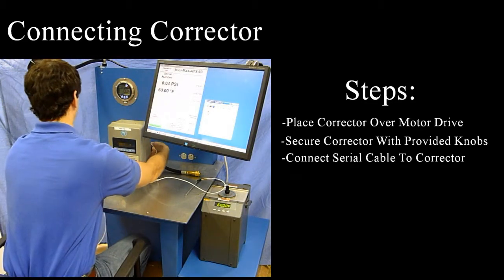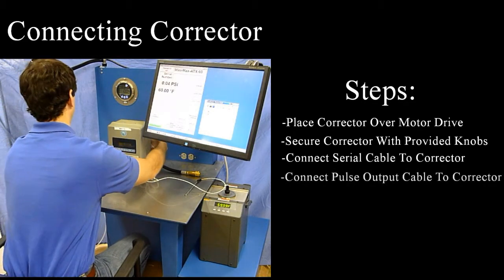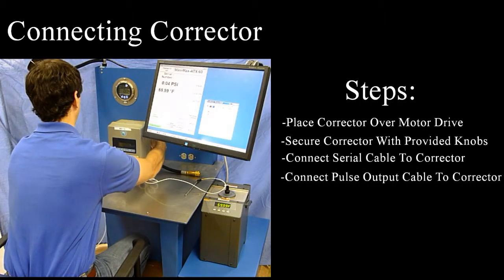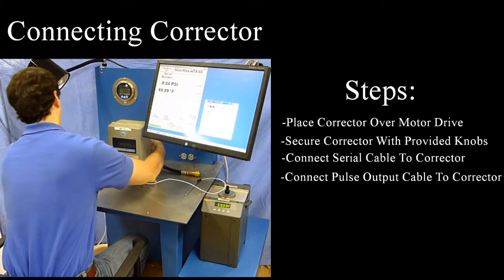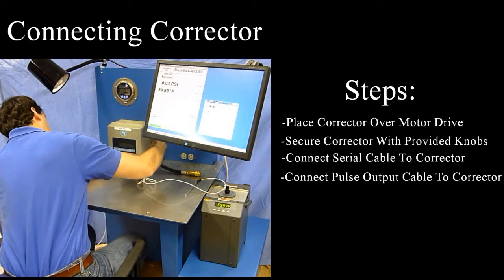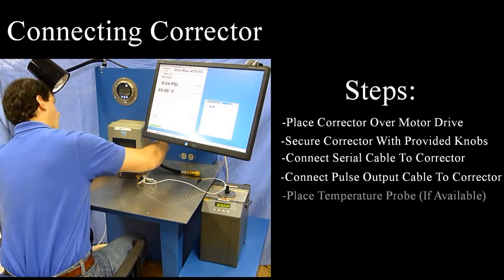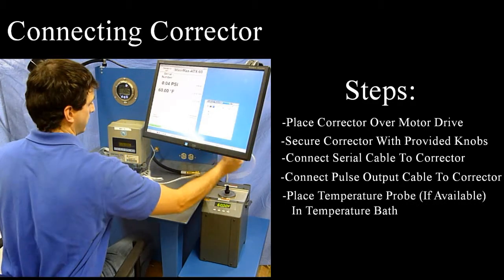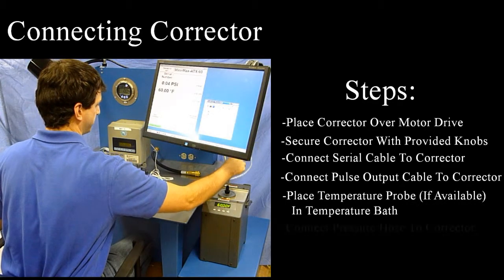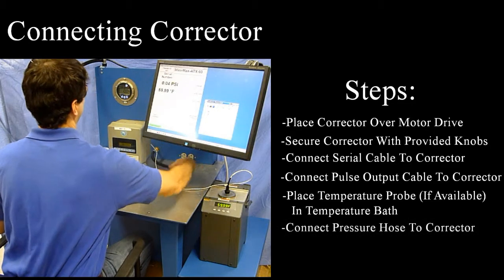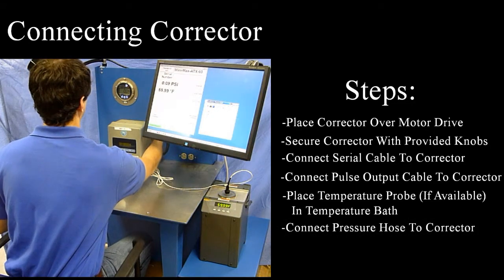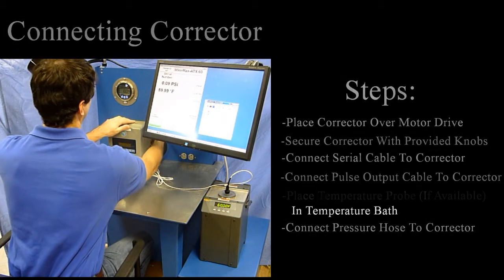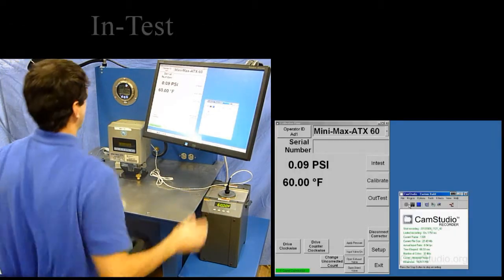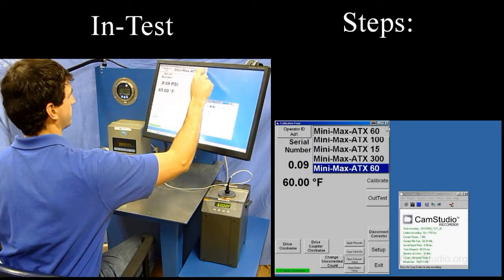The operator then connects the pulse output for both corrected and uncorrected counts to the on-stand cable. If the corrector has a temperature probe, it is placed into the on-stand temperature bath. Lastly, the pressure supply hose is connected to the corrector using a quick disconnect fitting. Once the corrector has been connected to the stand, the test can begin.